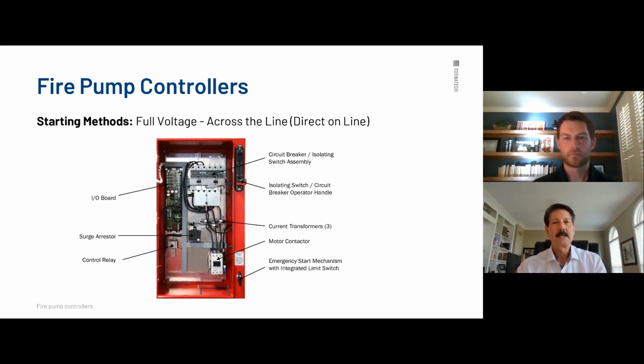I need the HP and I need the full load, or the HP and the voltage. Now on higher horsepowers, we might get into the fringe area where we might say, hey, we need to see the motor data sheet because we want to see what the amperage draw is. Again, this is typically, you're talking direct on line, 6 times full load amperage. You're talking small to medium horsepower motors, 480 volt, it'd be typical.